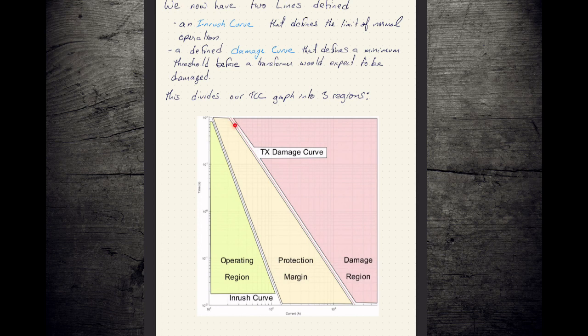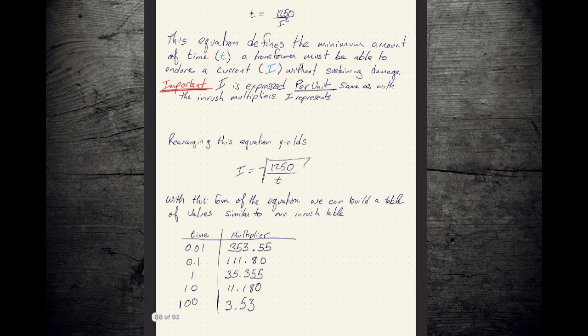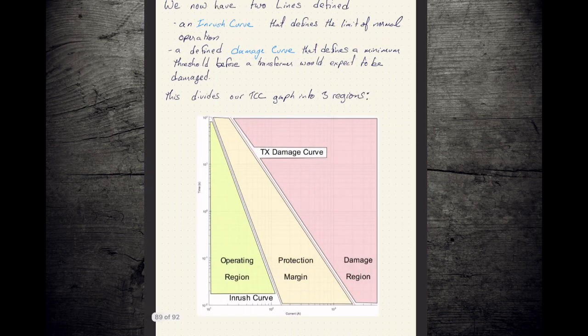And then we have another line. And if you take this equation and you pick some times and plot it out in a log-log graph, this also gives you a very nice straight line. And so this is the boundary where if you are above that, you've probably cooked your transformer, which is unfortunate because they're expensive and difficult to replace and take potentially 16 weeks to show up on your doorstep from when you order them. So you don't want to be blowing up transformers if you can at all help it. Really, that's the point of putting a fuse on it. So you blow the fuse, which is inexpensive and easy to come by, rather than the transformer, which is expensive and not.